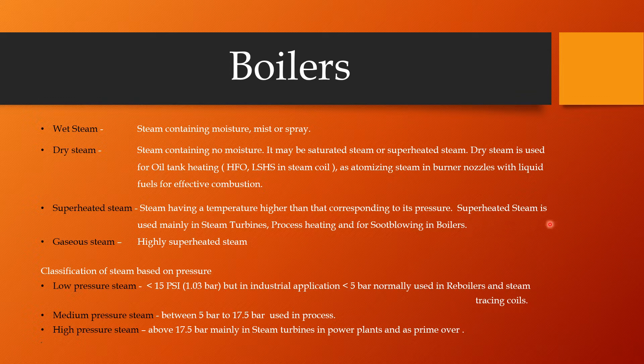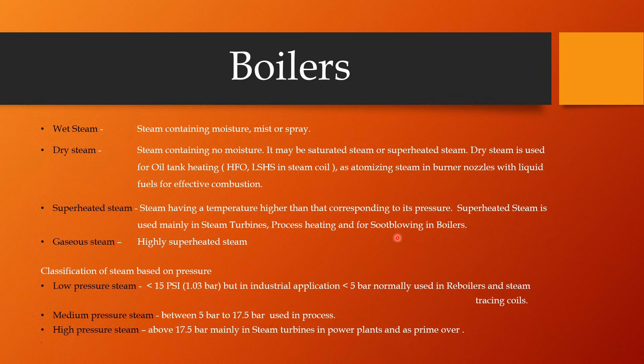If dry saturated steam or dry steam is used, when it comes in contact with the soot blower in the external pipeline, moisture will form and that will stick to the soot — so it cannot be removed. That will lead to failure of heat transfer and reduce the heat transfer rate. So we have to use superheated steam only for soot blowing, particularly in solid fuel firing and oil firing.